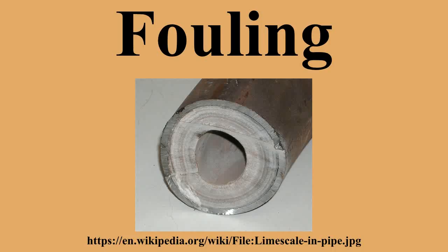Deposit composition can also be important. Even minor components of the deposits can sometimes cause severe corrosion of the underlying metal. There is no general rule on how much deposit can be tolerated. It depends on the system. In many cases, a deposit even a few micrometers thick can be troublesome. A deposit in a millimeter range thickness will be of concern in almost any application.